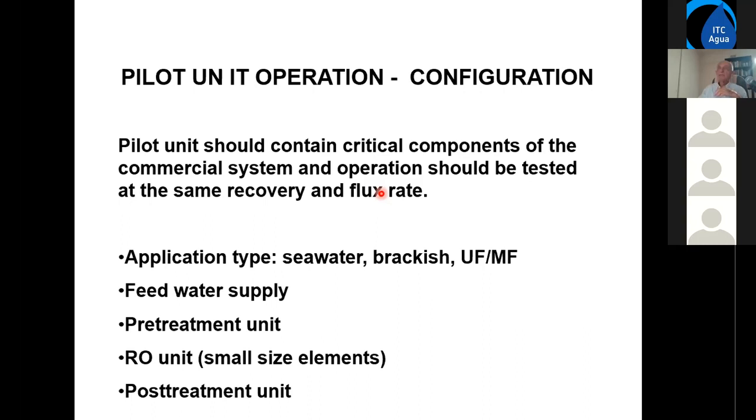Now, on the other hand, when we operate the pilot equipment, this equipment should operate at the process parameters of the commercial plant. So if we want to know if there will be scaling, we have to operate the last elements at the same flux as in the commercial system. This sometimes requires an interstage booster. And if you operate the filtration unit, it should operate at the same filtration flux, the same intervals between backwash, and so on.